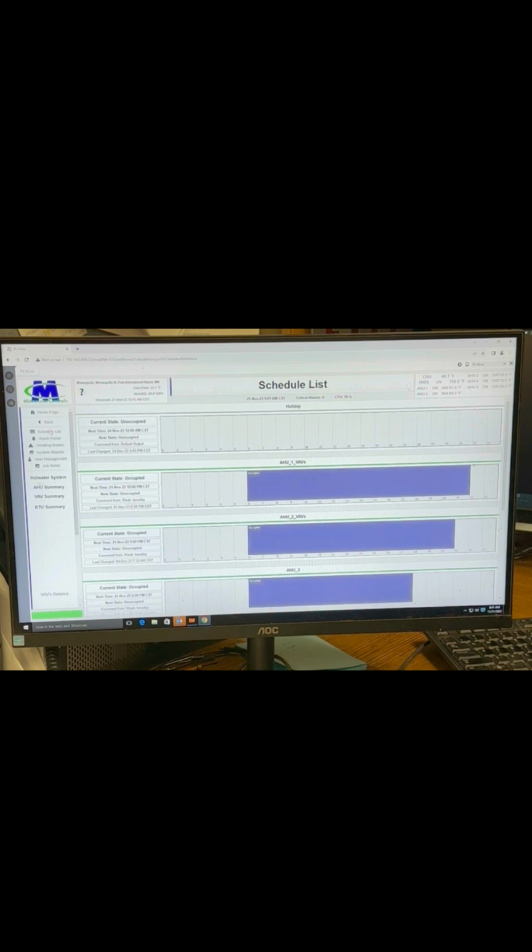And something about the fin tube for the gathering space? Nope, you don't want to schedule on that, right? All I'm going to do is program it to a set point and have it out on the screen. So you set that set point, it's going to modulate that fin tube radiation to maintain that set point, period. And then you change the high-low on that so it doesn't kick on the air conditioner, and then the fan should not go on either. No, unless it hits its unoccupied cooling set point. Gotcha, okay. And hopefully it shouldn't hit.